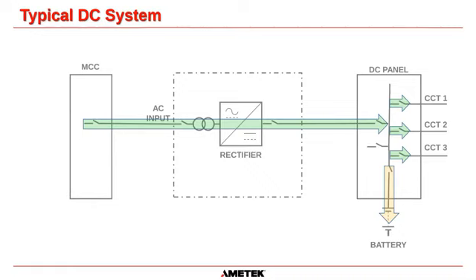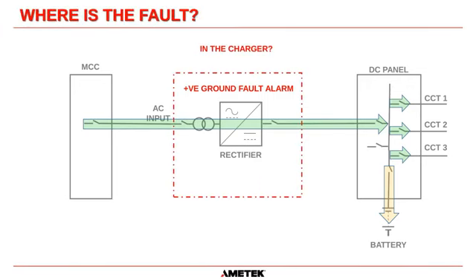Okay, so let's find the fault. Once again, back to our typical DC system, and we have a positive ground fault alarm on the charger. So what do we do? Well, the first thing we need to do is find out where the fault is. Is it in the charger, for example? What we want to do is break it down into sections and figure out where the fault can be.